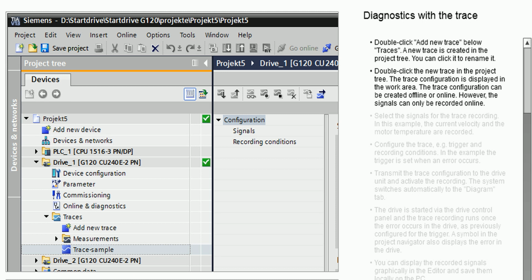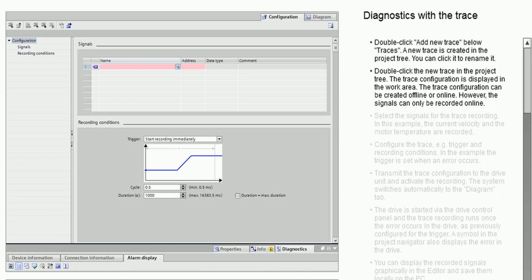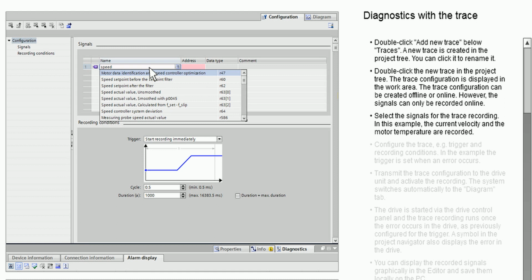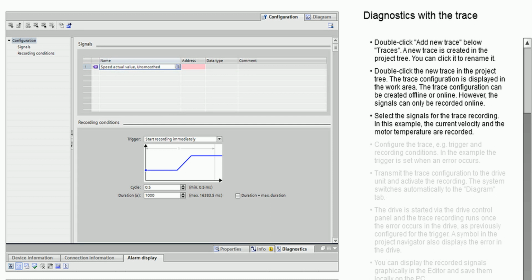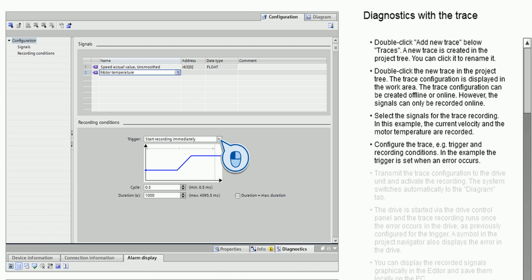The trace configuration can be created offline or online. However, the signals can only be recorded online. Select the signals for the trace recording. In this example, the current velocity and the motor temperature are recorded. Configure the trace, for example, trigger and recording conditions. In the example, the trigger is set when an error occurs.